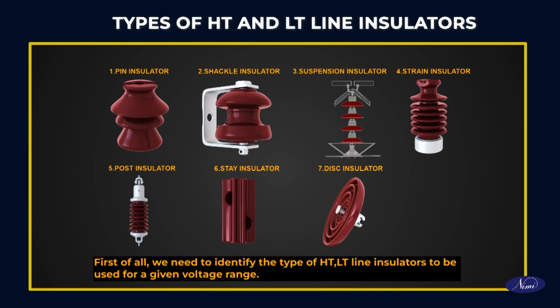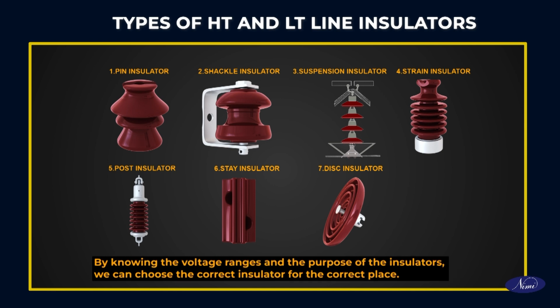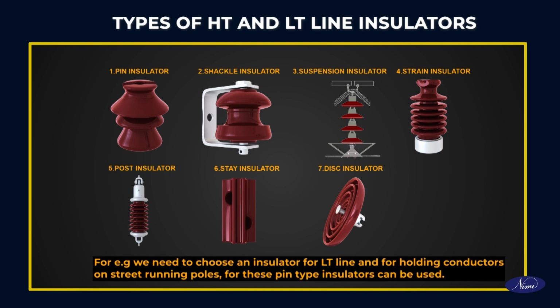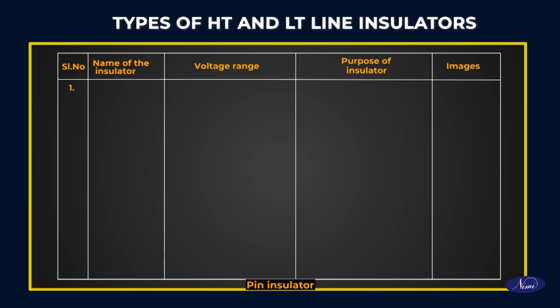First of all, we need to identify the type of HT-LT line insulators to be used for a given voltage range. By knowing the voltage ranges and the purpose of insulators, we can choose the correct insulator for the correct place. For example, we need to choose an insulator for LT line and for holding conductors on street running poles. For these, pin type insulators can be used. Pin insulator.